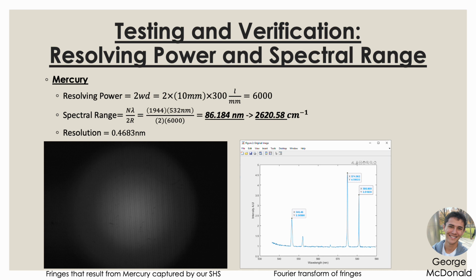0.4683 nanometers. Now the spectral range is just the number of pixels times the wavelength of the laser divided by twice the resolving power. And this results in a spectral range of about 86.184 nanometers, which is equivalent to about a Raman shift of 2620.58 inverse centimeters. So interestingly enough, we can pick up more Raman shifted frequencies compared to when we were using a 785 nanometer laser.